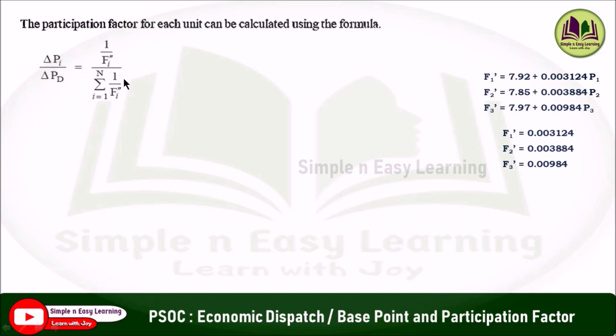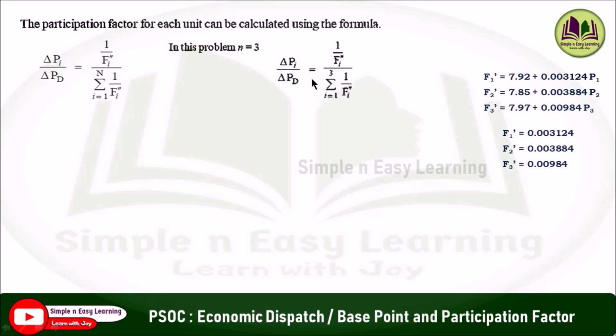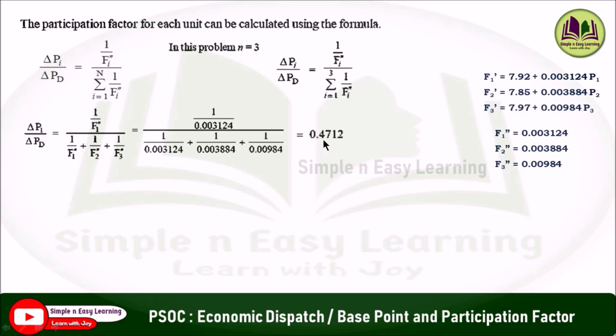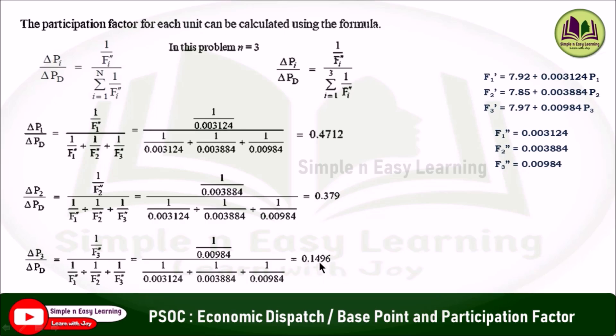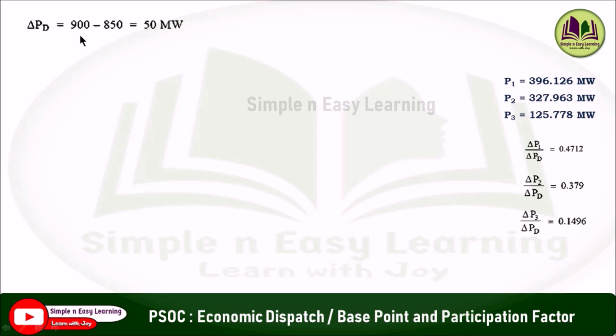The participation factor for each unit is: ∂Pi/∂Pd = (1/fi'') / (summation of 1/fi'' for i=1 to 3). For unit 1: ∂P1/∂Pd = (1/f1'') / (1/f1'' + 1/f2'' + 1/f3'') = 0.4712. Similarly, ∂P2/∂Pd = 0.379, and ∂P3/∂Pd = 0.1496.